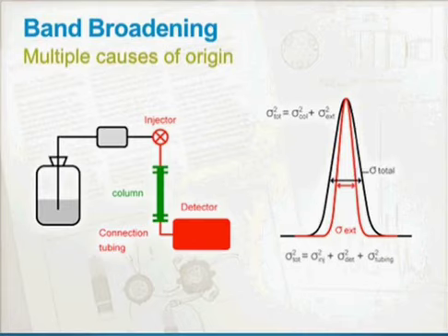And we learned that through hard experience, right? We have sample losses if the distance is long. We reduce peak concentrations if the distance is long. We make a horrible mess of a peak tail. All these things have led to the lore in the field that you really shouldn't be touching anything post-LC. And I would rather say you really shouldn't be breaking any of the accepted rules in fluidics post-LC. And so our system that we developed with you allowed us to achieve, in fact, better peak definition going into the mass spectrometer than we would have just by coupling the LC directly to the mass spec.